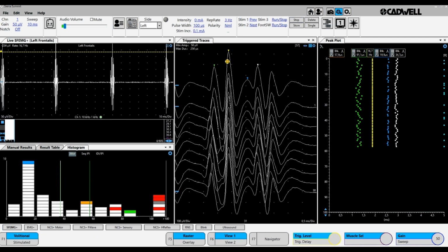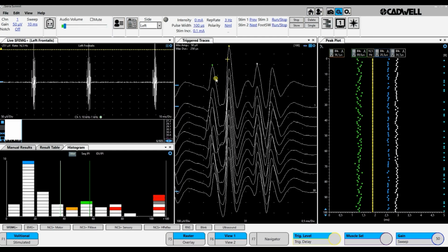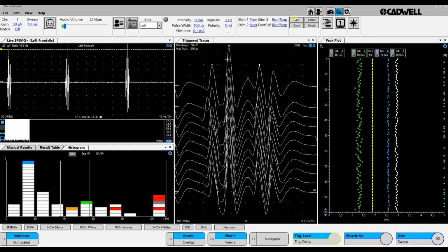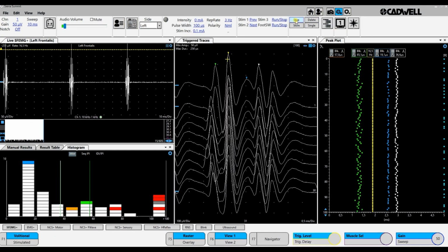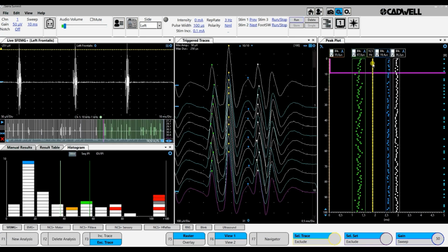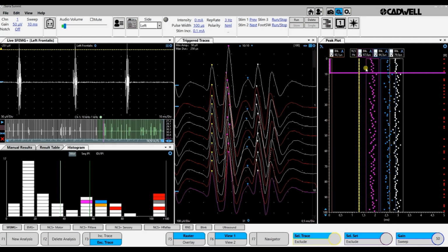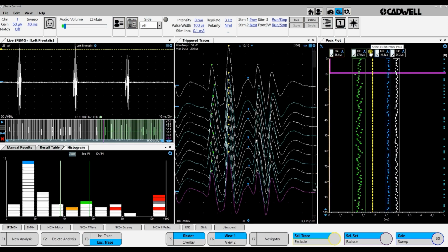Here's multiple recording with complex signals, and we trigger on the second one, and when I stop, it keeps the second. We could have triggered on the first one, but then the summated jitter is much larger, and therefore we go over and trigger on the second one. This jitter is 87 and 19 and 36. So in the same motor unit, you can have different abnormalities among the motor endplates.